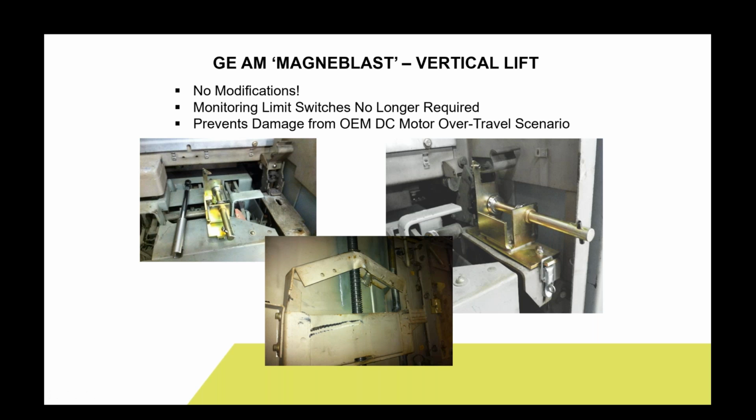So we even have, I think, a design that is beyond the original OEM solution with the motor. We run at a little lesser speed, a little more smooth in the operation, that we use for this breaker, but we're also not trying to detect those mercury switches. We want to run the breaker all the way to its full stop and see that it's fully seated. We just do it through torque monitoring, not through any kind of contacts or control circuits in the gear.